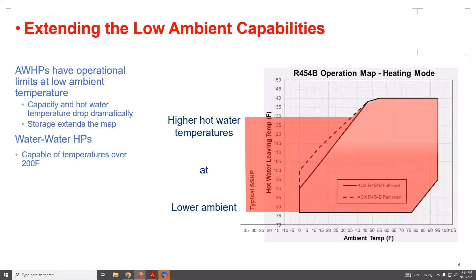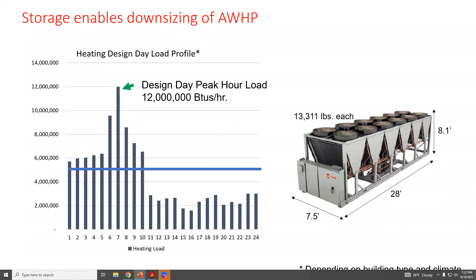This slide reiterates what Tyler talked about regarding downsizing your air source heat pump. If we look at this building load and heating profile across 24 hours for another Class A office space, our peak day heating load at 7 a.m. might be 12,000 MBH. If we wanted to accomplish this with all air source heating products, it would mean we need roughly 10 air source heat pump units, which takes up a lot of roof space and energy.